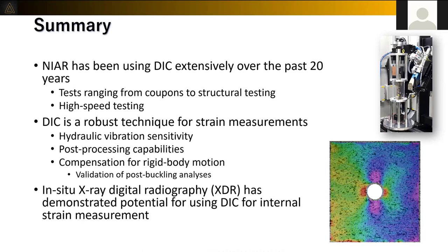DIC is a robust technique, like I mentioned before, very user-friendly on hydraulic test frames because of the rigid body motion correction. We have a lot of bells and whistles for post-processing the same set of data. We actually did a study with industry partners, including Spirit AeroSystems, Airbus, Textron Aviation, and Bombardier, where we looked at the same data and used multiple different software systems to reduce the data. ARAMIS gives us a lot of flexibility to use the same data in multiple different ways.